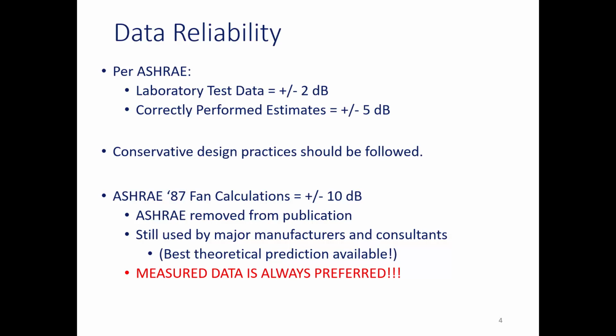It's usually able to ramp up to whatever's needed. Because of that, systems are designed so the worst case scenario is the only time it's running at 100% - maybe only a couple days out of the year when it's at maximum capacity and the noise is greatest. So most of the time, even if you design right on target and it ends up being 5 decibels higher than designed, that VFD kind of saves you in the end.